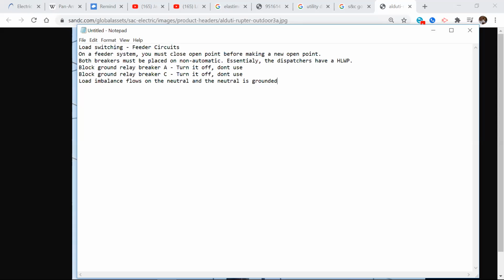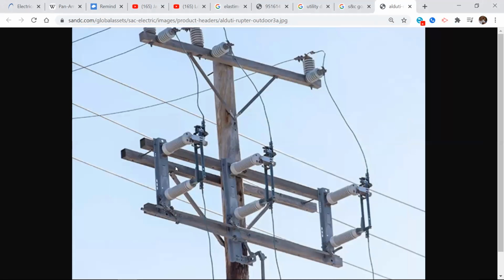All right, so in the situation where I'm opening this switch right here, I've got 300 here, 300 here, and 0 here, where it should be. That load imbalance, because I'm missing it, is flowing on the neutral. The ground relay in the substation is going to say, I've got amperage on the neutral. And what's it going to do to the breaker? Trip. It's going to trip the breaker. There you go.